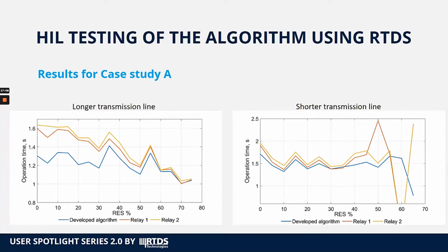For case study A, which represents swings between two parts of the network, we can see that the developed algorithm shows faster operation times than the impedance-based protection relays in all of the renewable energy penetration scenarios. In addition, it has to be noted here that the impedance-based protection devices fail to operate for the 60% renewable energy penetration scenario for the shorter transmission line between two parts of the network, whereas the developed algorithm operated successfully.